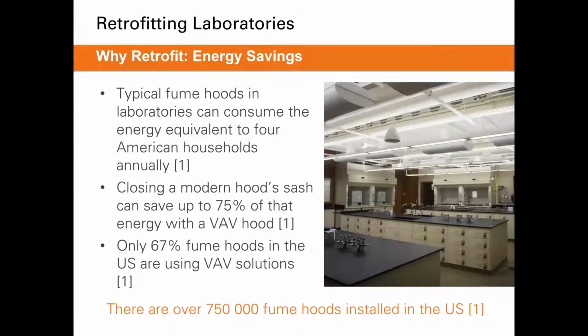So the second point here, closing a modern hood sash can save up to 75% of that energy with the VAV hood. VAV hoods, or variable air volume hoods, are hoods where when you move the sash, the air valve serving that hood will open or close to let more or less air through the valve in order to maintain that safe feet per minute or face velocity through the sash opening. What we're comparing it to here would be a constant volume or a bypass hood, where rather than the air valve compensating for that change in sash height, there's a bypass that lets more or less air flow through it when the sash is opened.